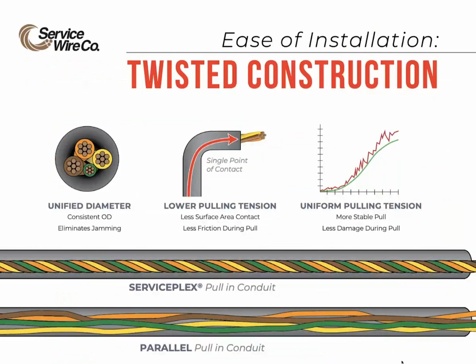ServicePlex is an assembly of quality Service Wire single conductors twisted together to create a uniform construction, effectively functioning as a prefab wire pull. This easy to install multi-conductor cable is a great solution for longer pulls. What may have required 4 individual reels before could easily be replaced with a single reel of ServicePlex. The prefab cable reduces the time it takes to execute a pull, allows you to pull the wire even faster, and requires fewer reels on the job site. Contractors who use ServicePlex reported 50 to 70% combined material and labor savings.